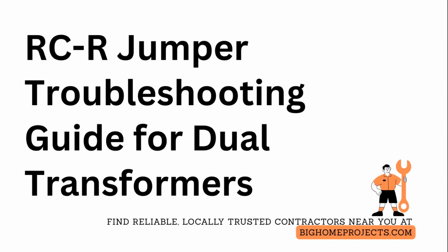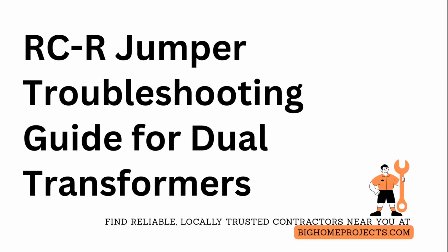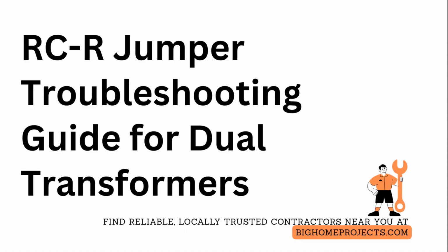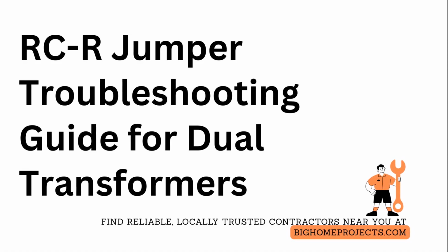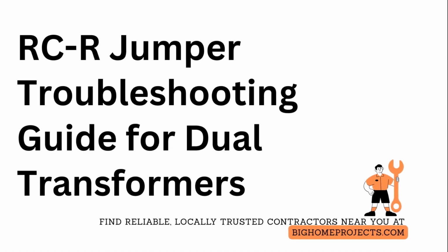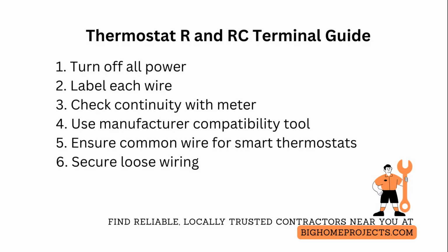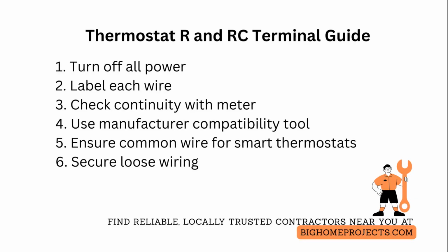RC and R on a thermostat tell you which power feeds control heating and cooling, so you don't accidentally crosswire systems or blow a transformer. For a single transformer system, you will usually see an R terminal supplying 24-volt power and a jumper to RC, so both cooling and heating controls are powered.